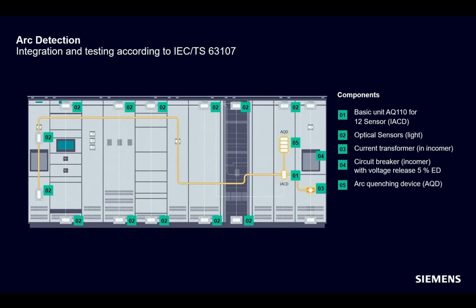In order to avoid false triggering by other bright events, the sensors are precisely matched to the spectrum of an arc fault. And the sensors are also available with different light sensitivities, depending on where the sensor is to be installed. A further safeguard is the use of current transformers in the incoming feeder as an additional triggering criterion. Only if a steep rise in the current is detected in addition to the light signal, the trip signal is sent to the circuit breaker. All of this happens very fast, within about 15 milliseconds until the circuit breaker has switched off. This means that the impact on the system is significantly reduced.